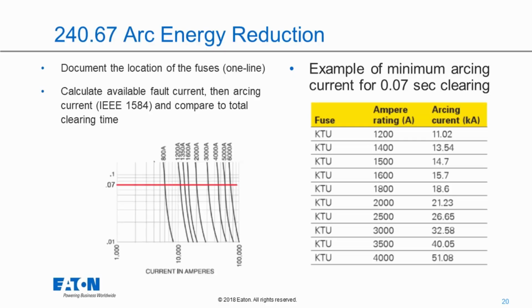If you look in the 2020 code change document, we actually included a table that shows you, for a specific type of fuse, this being the KTU, the minimum arcing current such that we would guarantee clearing of 0.07 seconds. So for instance, if we had a 1200 amp KTU fuse, as long as my arcing current was 11.02 or higher, I do not need to go any further. The fuse will provide the required clearing time of 0.07 seconds or less, and I'm fine. However, if my arcing current was 10,000 amps, then I would need to investigate other types of technology and make sure that it will operate within the arcing current time.